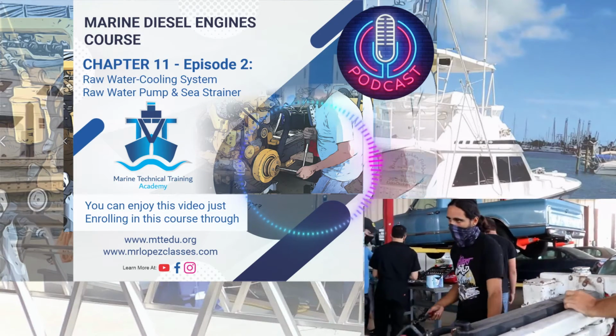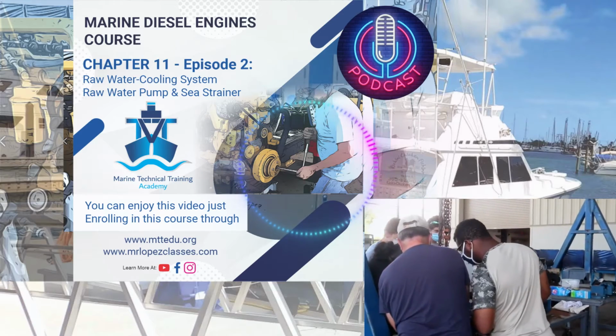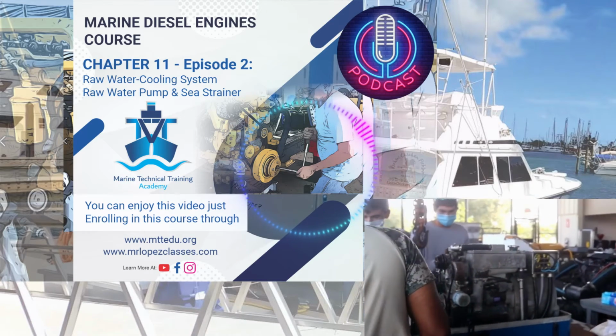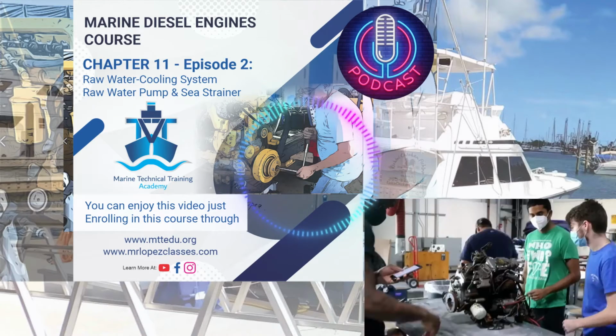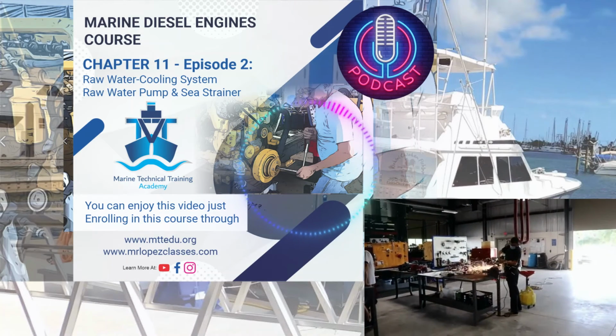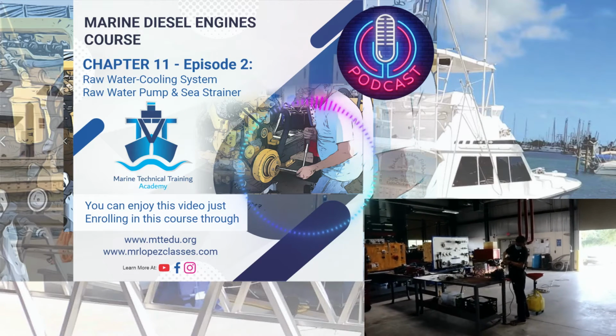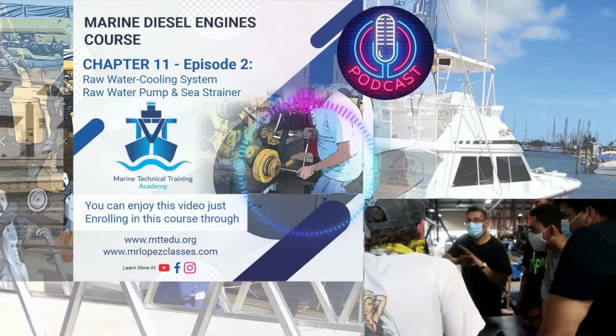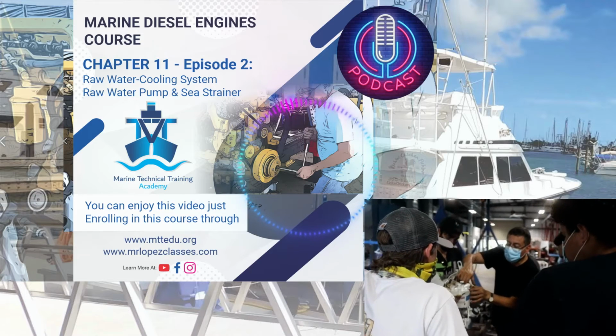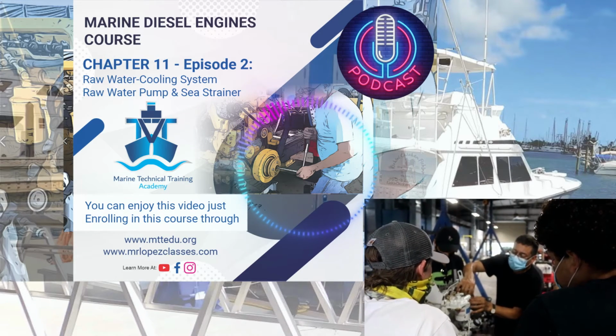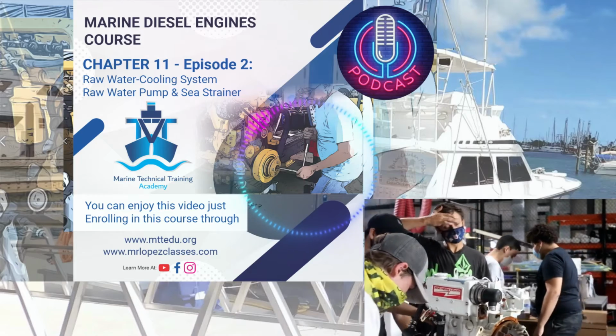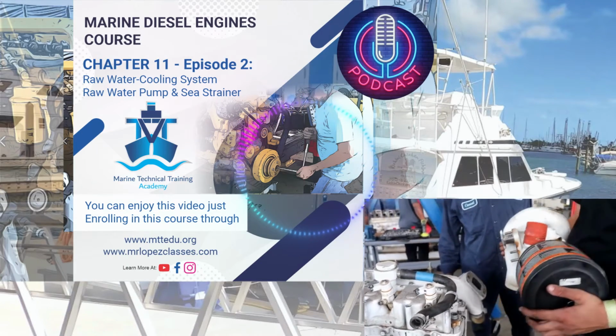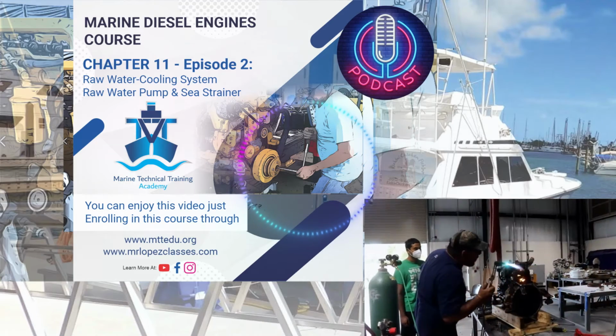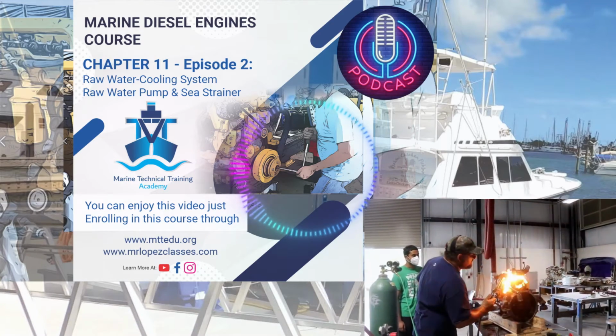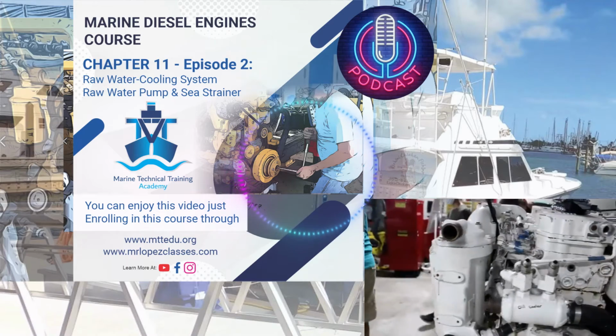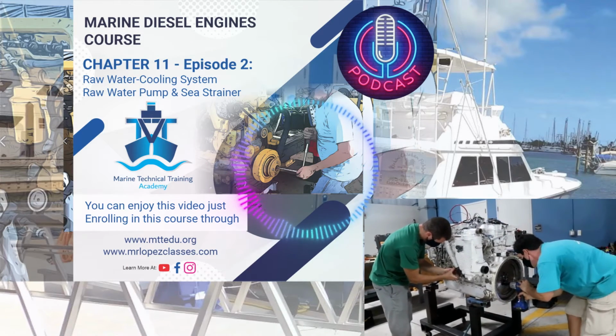Immediately after you remove the impeller from the pump, check with your fingers the quality of the housing. Check that the half moon is firm, is located over there, and check the groove and verify that the groove is clean. And verify that you don't have play on the shaft and the pulley. No lateral play. And verify that you don't have leaks over there. In other words, the seal is in good condition, the half moon is in good condition, and the shaft is in good condition. We are ready to put the impeller back in.